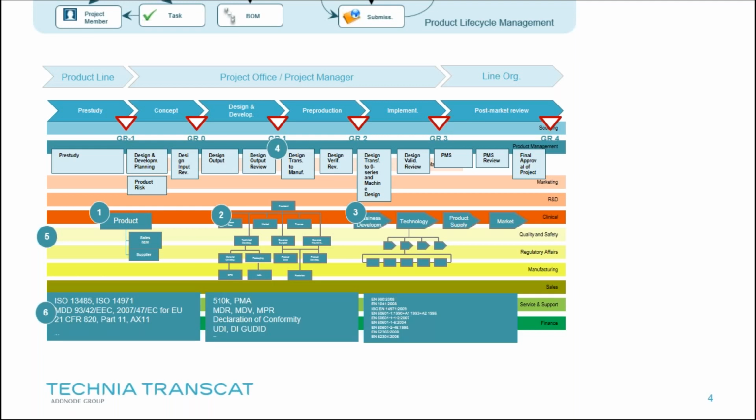And when we implement this, we make sure that it's set up in line with the current regulations and requirements, whether it's European or Canadian or US requirements. We set it up in line with the submissions required for different markets, whether it's self-declaration, as here in Europe, or if it's submission based for different regulations.